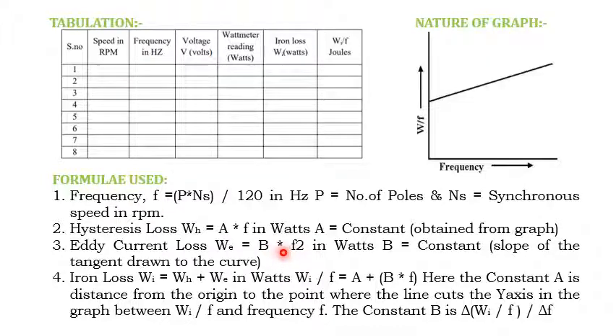B is nothing but the slope of the tangent drawn to the curve. This is your straight line. You just need to draw one tangent to this line, then calculate the slope of this straight line, and that represents B. Then the iron loss is the combination of the hysteresis loss and the eddy current loss. So Wi divided by F equals A plus B into F.